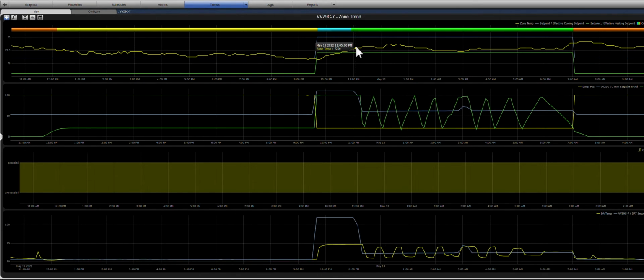We have two conditions here. One is the control of the controller to decide how much air to put in the space, and the other is the static pressure of the entire system, making sure it has enough. Remember, these are pressure-dependent systems. We can't read the exact value of CFMs coming in and make a calculation to do so. We just have to tune these so we don't give people bursts of heat, but we have a steady climb of BTUs per hour of comfort change.